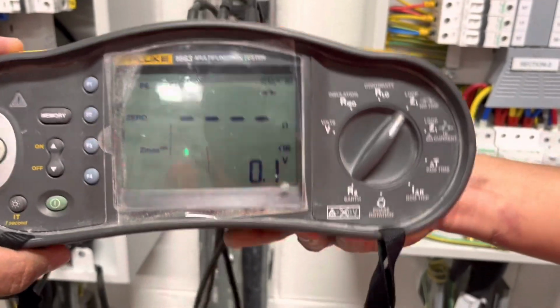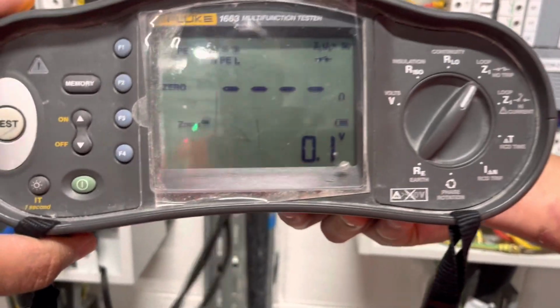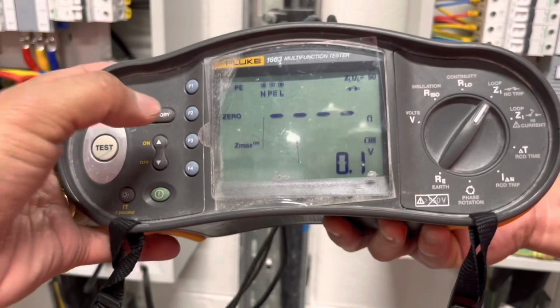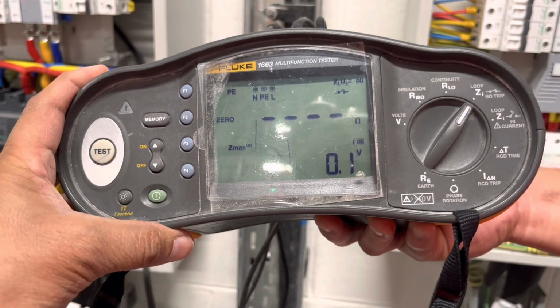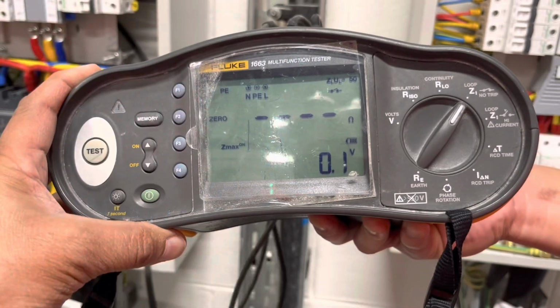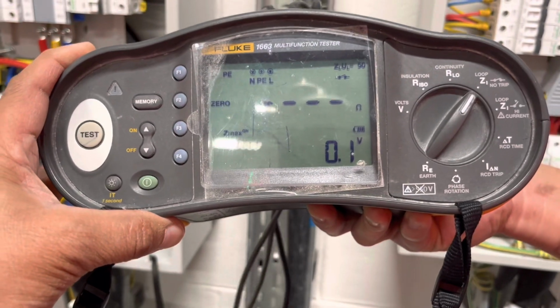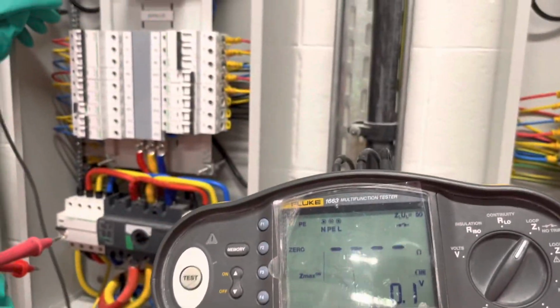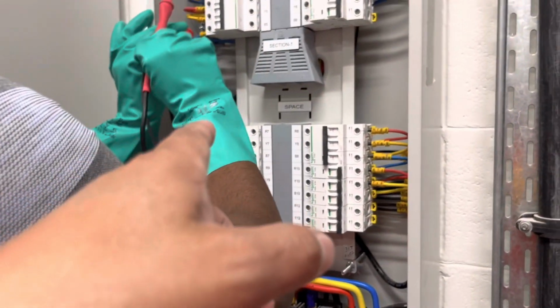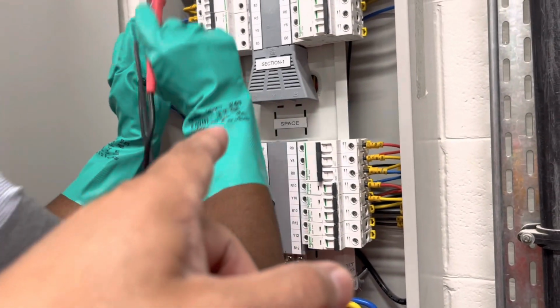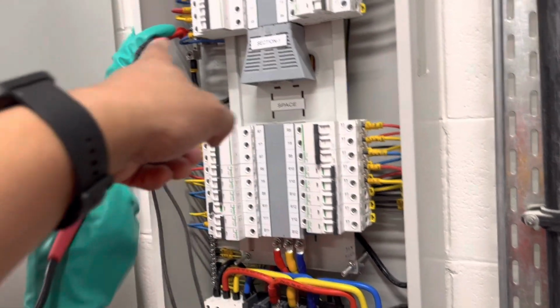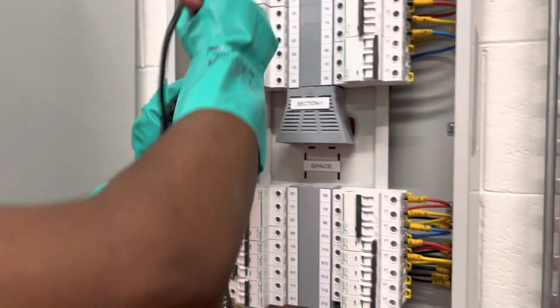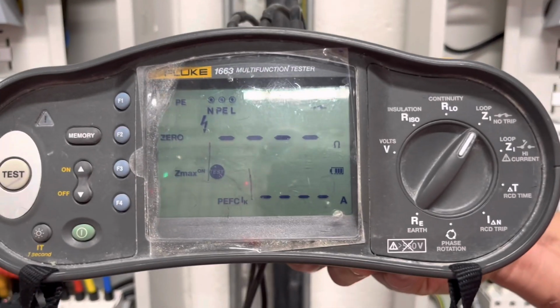So the continuity. This is the loop test. Yes, loop test. Live test. Loop impedance only. This is not the tripping. The loop impedance. What is that one? Neutral. That one neutral. Neutral, earth. This one earth. The light. Loop test, this is the impedance. We will see how much the impedance is.